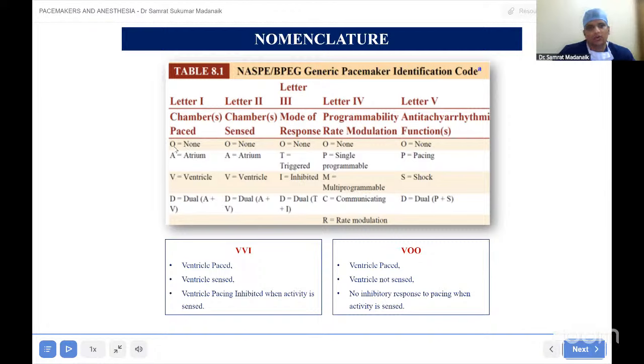anti-tachyarrhythmia functions. So O means none, A means atria, V means ventricle, and D means dual, that is atria and ventricle. So for example, suppose a pacemaker nomenclature is VVI. Basically what is happening here is that this pacemaker is ventricle paced, it is ventricle sensed. And what does this I mean? It means inhibition. So basically ventricle pacing will be inhibited whenever activity is sensed. If your pacemaker is on this mode, it will pace the ventricle, it will sense the ventricle, and only if required, it is going to generate impulses beyond whatever levels you have set. Only after that will the impulse be generated and the patient be paced.